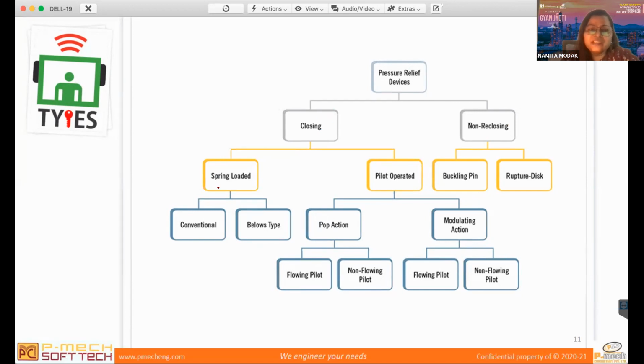So that is the difference between reclosing and non-reclosing. In reclosing, you will see spring loaded and again pilot operated. In spring loaded, we have the conventional type and the bellows type. If you have a back pressure to set pressure ratio of 10%, you go with the conventional type. If the back pressure to set pressure ratio is 30 to 50%, you will go with the bellows type. And if your back pressure to set pressure is more than 50%, you go with pilot operated type PSVs. Again, in pilot operated, you can see it's a pop action or modulating action. In pop action it's flowing and non-flowing, and in modulating it is also flowing and non-flowing. I'll show what is the difference between flowing and non-flowing.